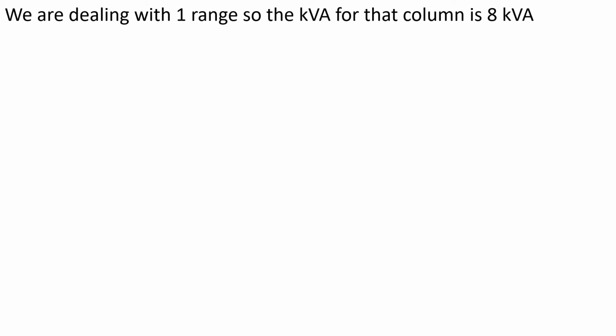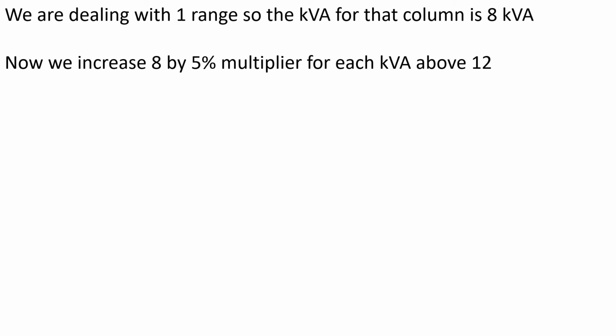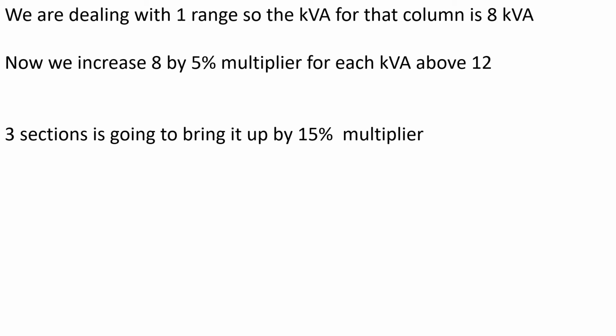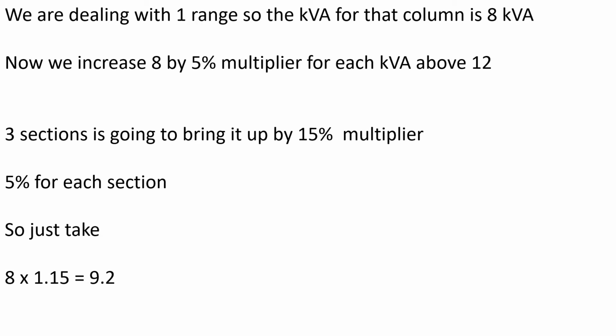We're dealing with one range, so the kVA for that column is 8 kVA. Now we need to increase 8 by a 5% multiplier for each kVA that is above 12. 3 sections is going to bring it up by a 15% multiplier. So just take 8 and multiply it by 1.15, and that is going to give you 9.2.